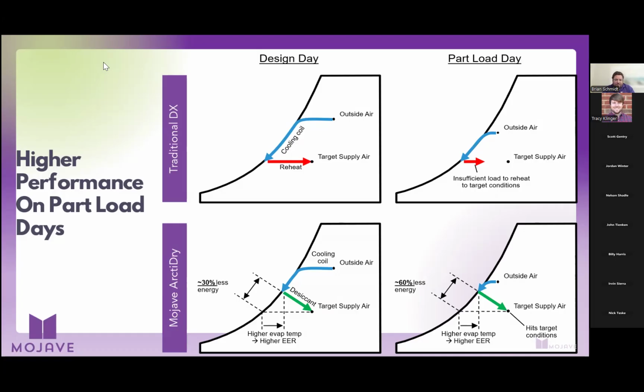Mojave's ArctiDry system, again, on design day, is going to have a little bit of that triangle cut off at the bottom. Let's just say hypothetically 30%. The lowest that I've modeled is about 25% at a 0.4% dehumidification day. So even at peak conditions, we are still about 25% more energy efficient. And then obviously during part load days, we get even more efficient than that. So the more of that triangle we can cut off, the less DX cooling we need to use to get to our target supply air condition, and the more energy we save.